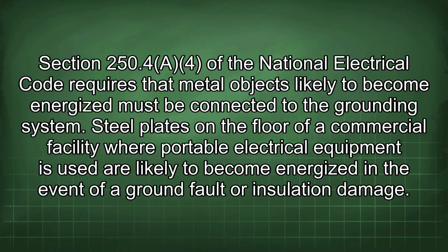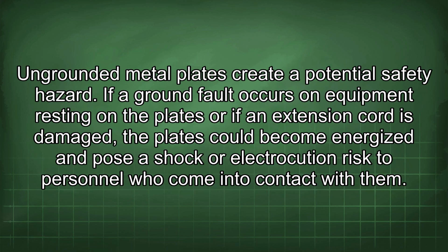Section 250.4(A)(4) of the National Electrical Code requires that metal objects likely to become energized must be connected to the grounding system. Steel plates on the floor of a commercial facility where portable electrical equipment is used are likely to become energized in the event of a ground fault or insulation damage. Ungrounded metal plates create a potential safety hazard.